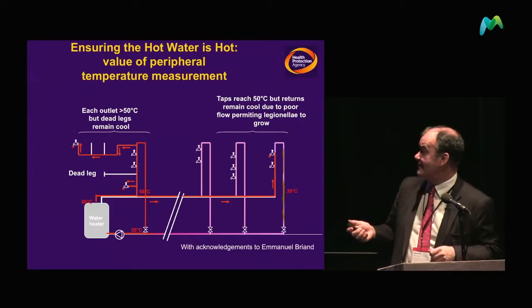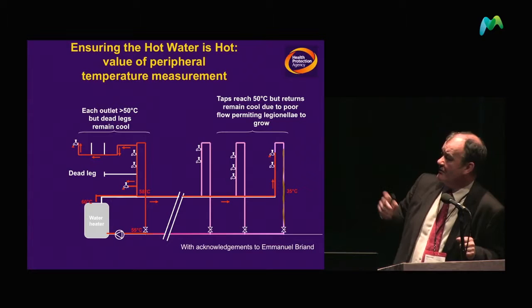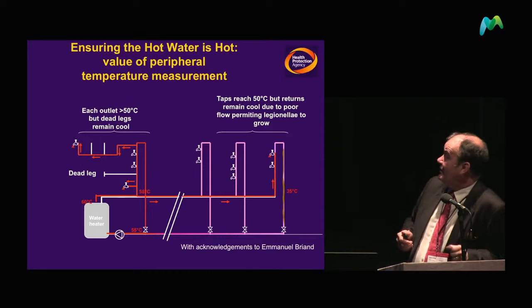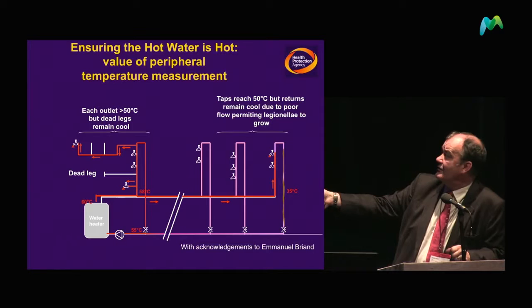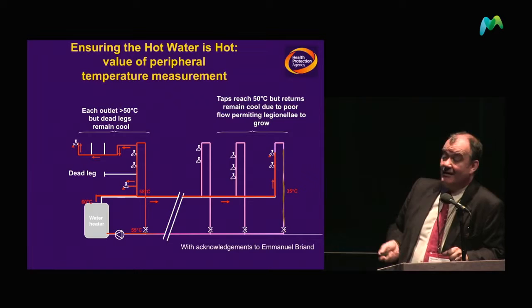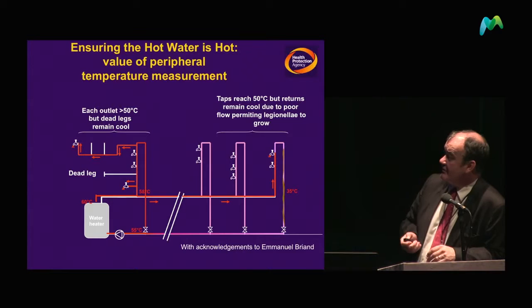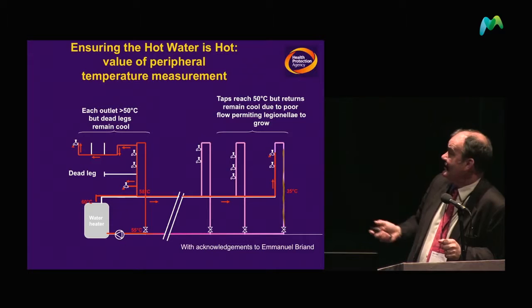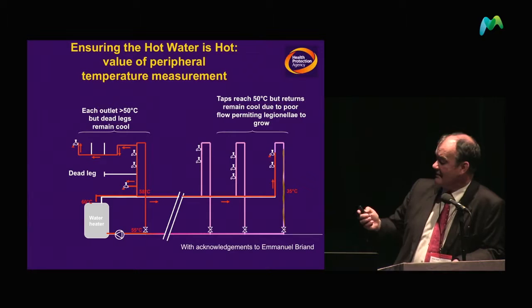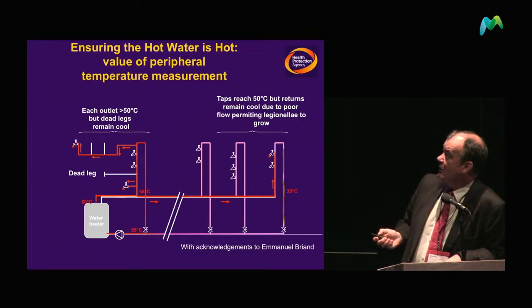This illustrates some of the problems — 55 to 60 degrees leaving the hot water tank and 55 degrees returning, as required by legislation. However, you can get dead legs where there is no hot water circulating, reaching temperatures of anywhere between 30 and 40 degrees — ideal reservoirs for Legionella — which can then intermittently work their way into the system.